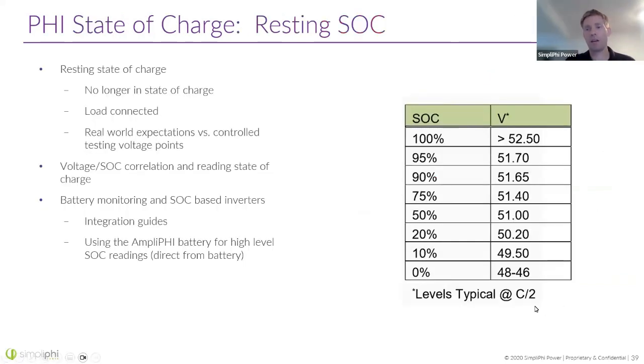Here are the levels at a C/2 rating. At a C/2 rating, we're looking at 50 volts as 20% state of charge, and 100% state of charge is less than the 53.4 I showed you earlier, because when the battery is discharging at a rate of C/2, there's a voltage drop inside the battery due to internal resistance.